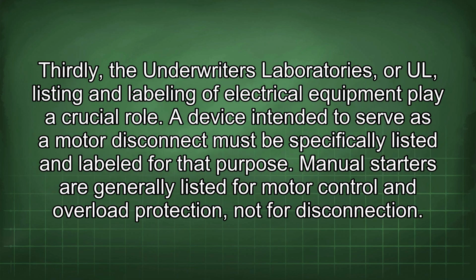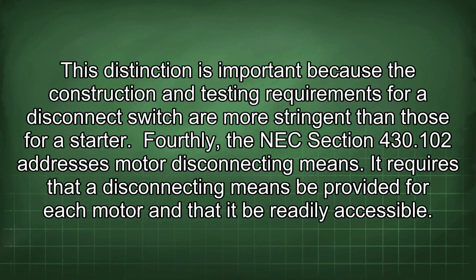Thirdly, the Underwriters Laboratories, or UL, listing and labeling of electrical equipment play a crucial role. A device intended to serve as a motor disconnect must be specifically listed and labeled for that purpose. Manual starters are generally listed for motor control and overload protection, not for disconnection. This distinction is important because the construction and testing requirements for a disconnect switch are more stringent than those for a starter.